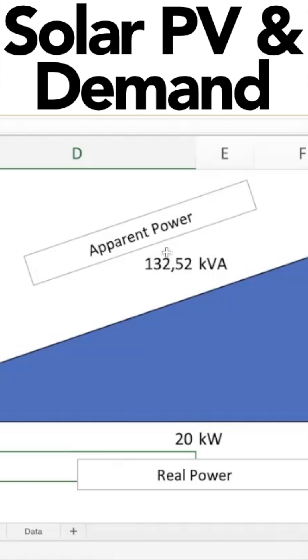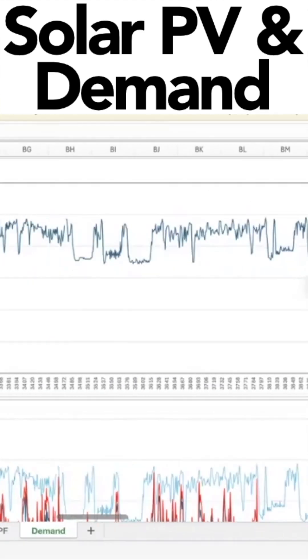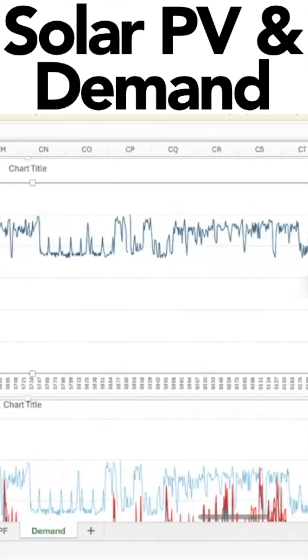Look at your demand. Your demand is still sitting at 132 KVA, even though you're only drawing 20 kilowatts from the grid. And that is because your reactive power component stays the same. So that's your reactive power for the entire year.